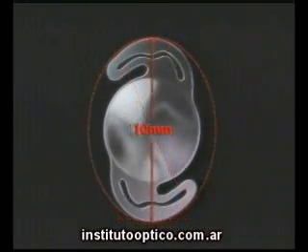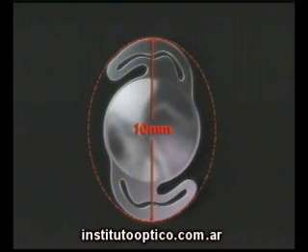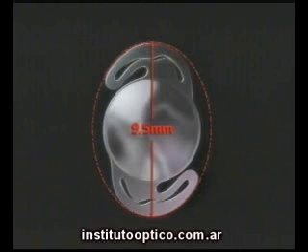If the capsule's equatorial diameter contracts to 10mm, a further contraction is prevented in one meridian by an interference of one part of the haptic with an adjacent part. Along this meridian, asymmetrical capsular contraction is subsequently prevented. The spring-like resistance of the haptic is then stiffened by new bending fulcra created by the haptic's interference with an adjacent part. This extra stiffness allows for some further contraction of the capsule along the adjacent meridians, and has the effect of preventing the contraction force along the 10mm meridian reaching a level sufficient to buckle the haptic. Ultimately, under severe capsular contraction, the haptic ends will reach the lens body, at which time the IOL is deformed in profile to an approximately oval or elliptical shape, which is resistant to any residual twisting and buckling forces likely to be applied by the capsule.